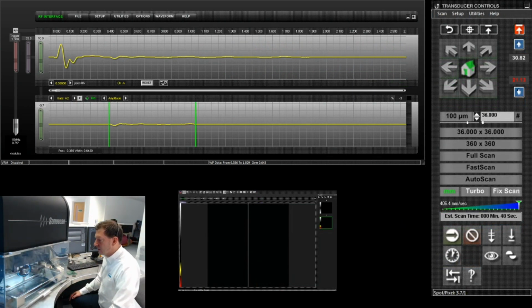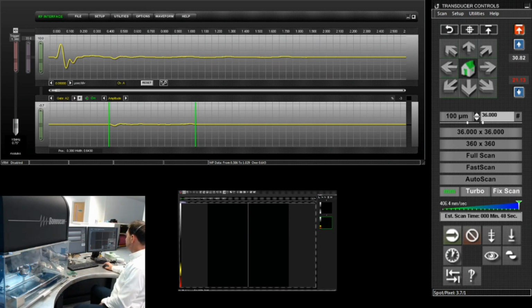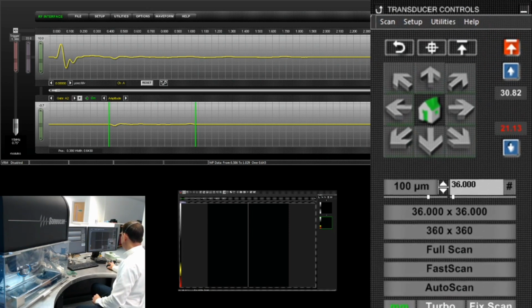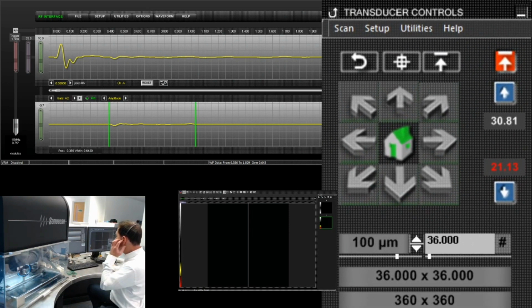So now that we have the transducer installed and the correct frequency selected on the software, we can move the transducer over the sample, ready for scanning. This is a manual operation, and we'll be using the transducer control window on the right side of the screen. So we have a group of arrows here around the home logo, and this is for controlling the transducer in the X and Y direction. And there's two smaller arrows up and down on the right side. They're for controlling the focus, or Z axis, of the transducer.